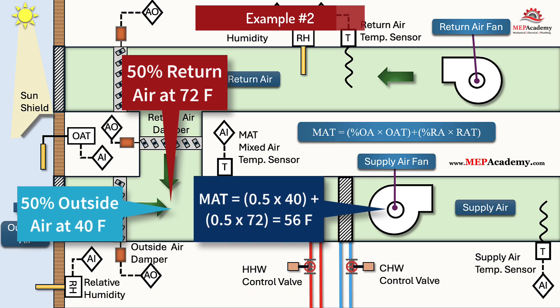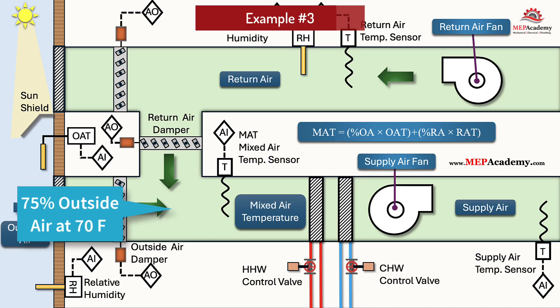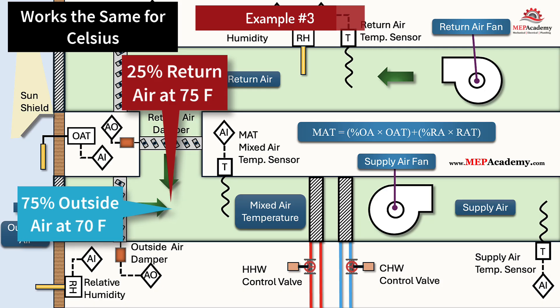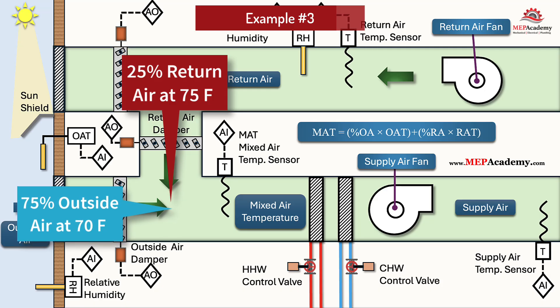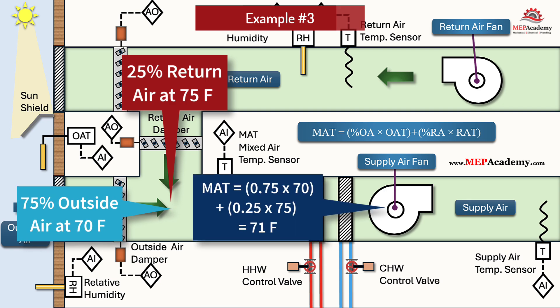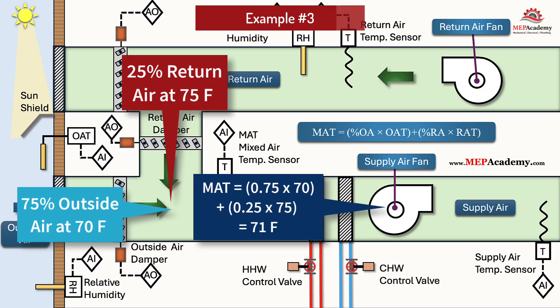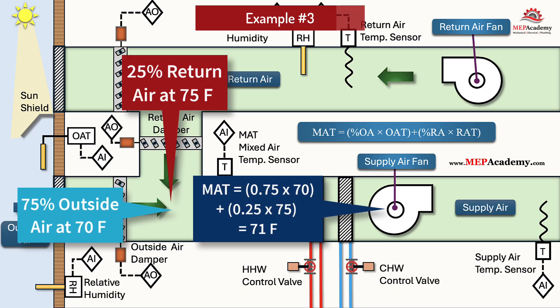Example 3 — 75% outside air, economizer mode: Outside air = 70°F, return air = 75°F, OA = 75%, RA = 25%. Mixed air temperature = (0.75 × 70) + (0.25 × 75) = 71°F. The coil sees 71°F entering air. This may or may not be a good setup depending on relative humidity — if the outside air carries a higher latent load than the return air, this could add significantly to energy consumption as the coil will need to remove excessive moisture in a wet coil situation.